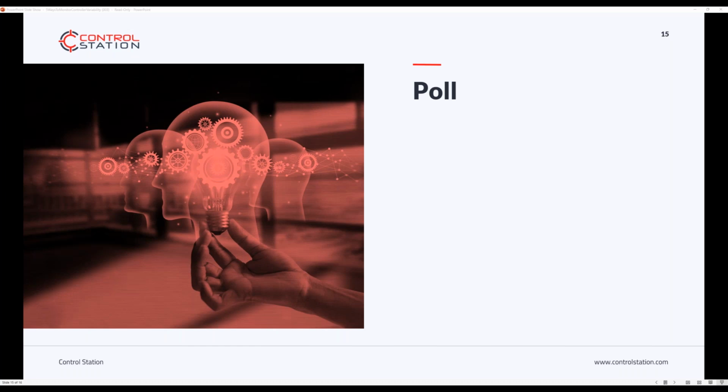It can start pulling in diagnostic information directly from the instruments. It can start to integrate with MES systems to let you know, hey, there's a valve that's been queued for a maintenance correction next week. And so the SCADA systems really start to be the kind of central warehouse of all the information needed to operate the plant effectively, not just the operator station, right?